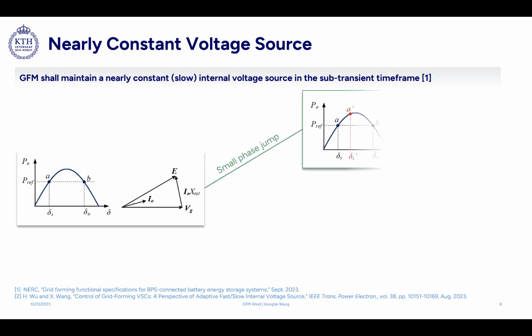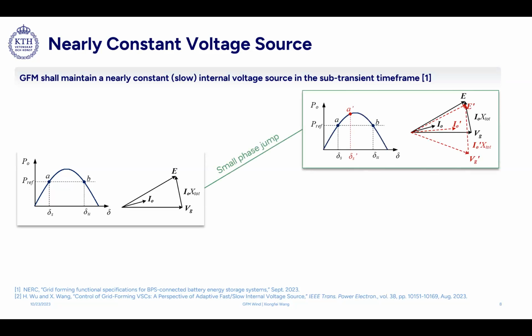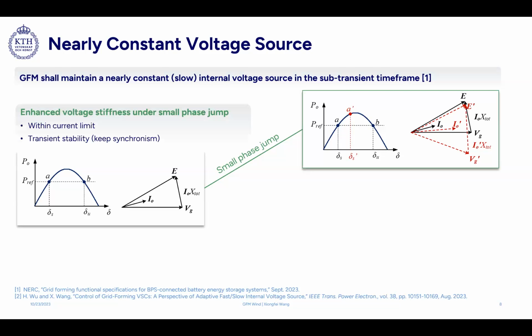But for a small disturbance, for example a vector shift or phase jump, this works very well. We keep the internal voltage phasor nearly constant, and then we have an autonomous current response. This is a kind of natural response without any time delay in the control. In this way, we can enhance the voltage stiffness, but within the current limit of the power converters.